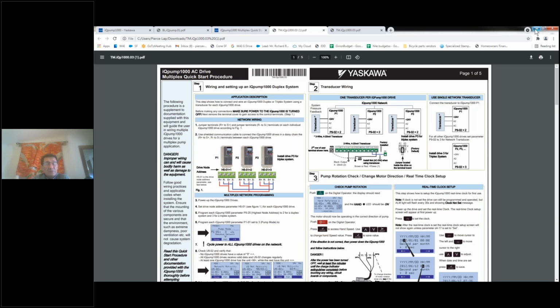And as a result, increased reliability. Why? Because you're sizing the drive to handle its environment on its own. You're not sizing it such that it needs a crutch. That's a very important design point. Air conditioning is a crutch, and it allows you to undersize your drive thermally. But when the air conditioner goes out, that undersized drive can't do the duty.